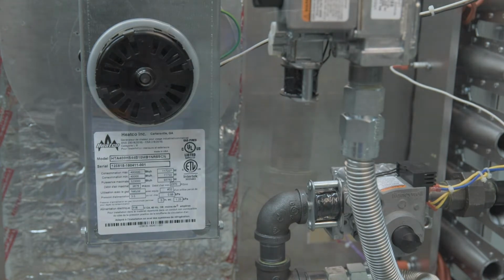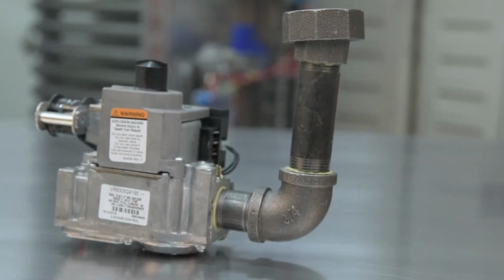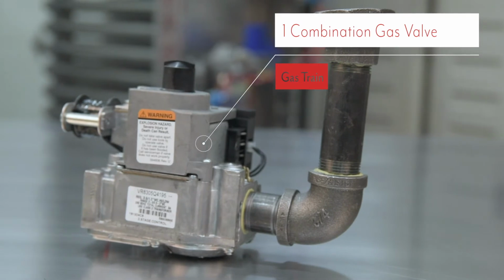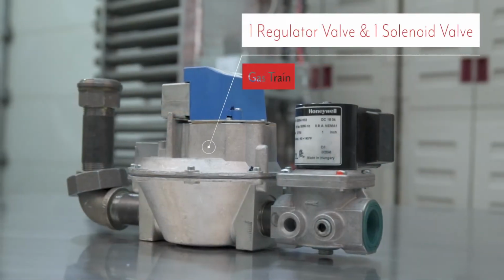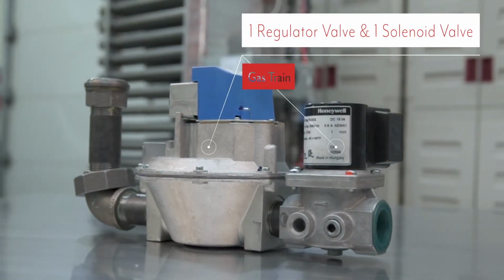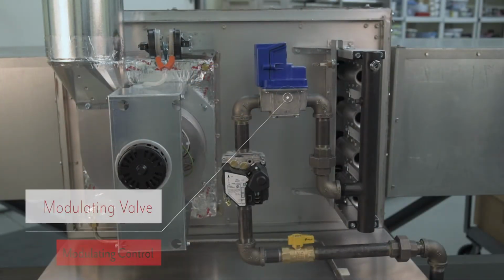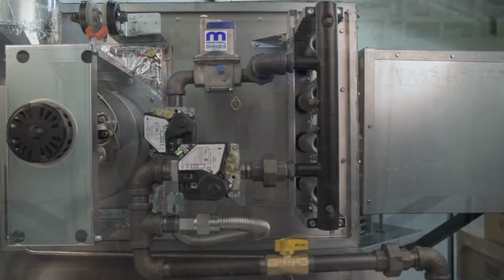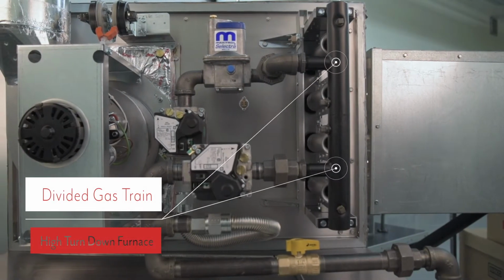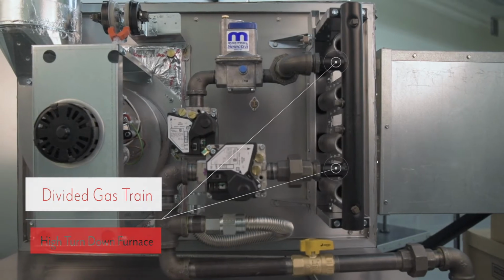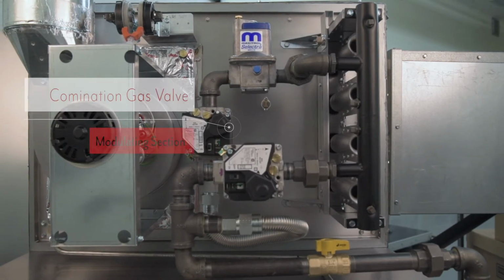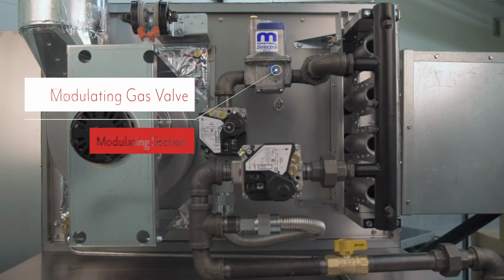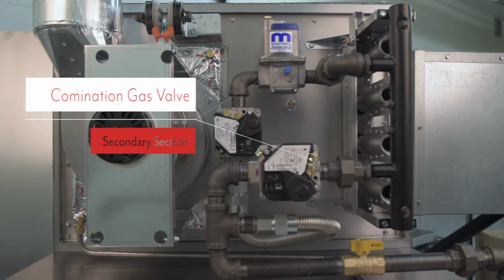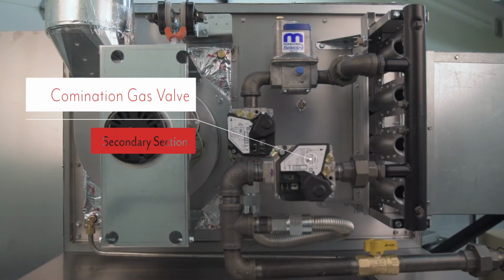the furnace. Based on the furnace BTU input, the furnace may have one combination gas valve or one regulator valve and one solenoid valve. If the furnace has a modulating control, there will be one modulating valve downstream of the gas valves. High turn-down furnaces of 10-to-1 or higher will have a divided gas train. The modulating section will have one combination gas valve and one modulating gas valve. The secondary section will have one combination gas valve.